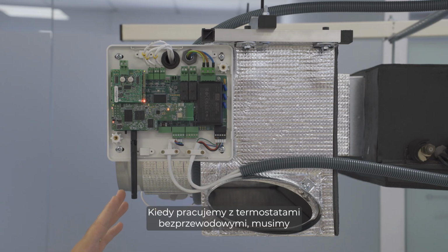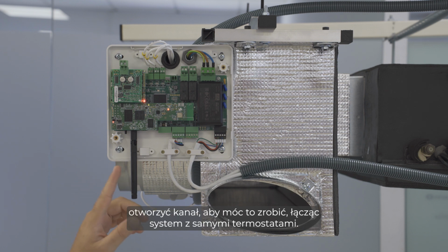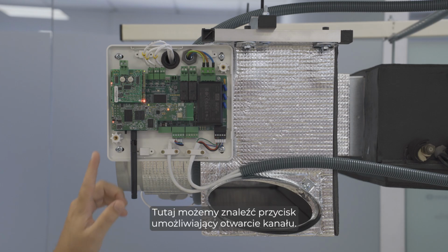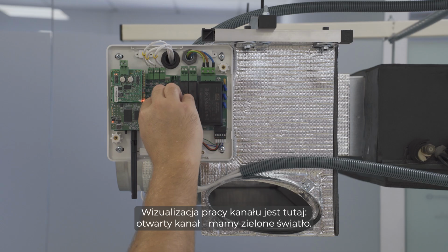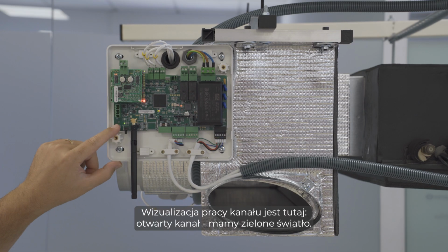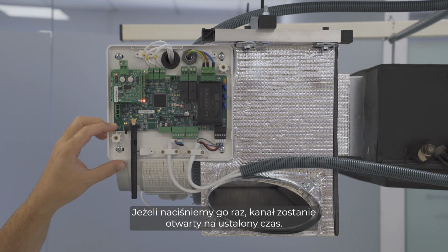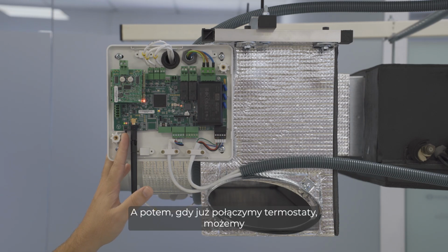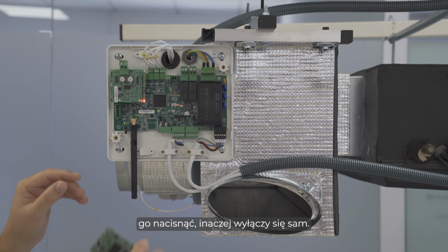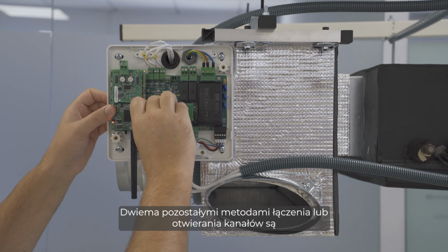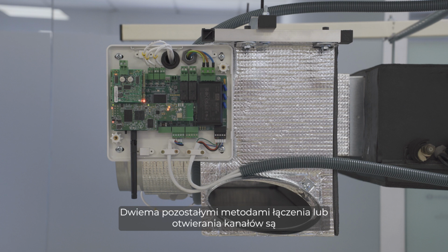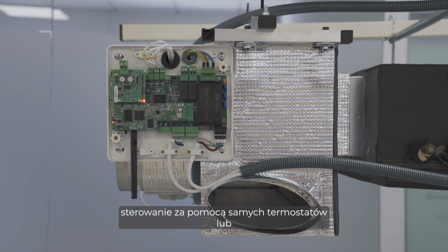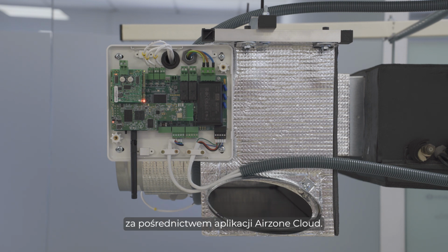When working with wireless thermostats, we need to open the channel to link the system and the thermostats. Here's the button to open the channel. We have just the green light; pressing it once opens the channel for a predetermined time. Once we've linked the thermostats, it turns off on its own. The other two methods for opening the channel are through the thermostats themselves or via the Airzone Cloud app.